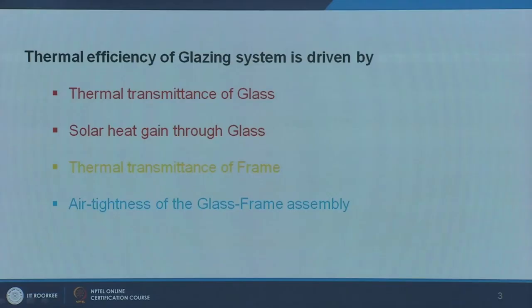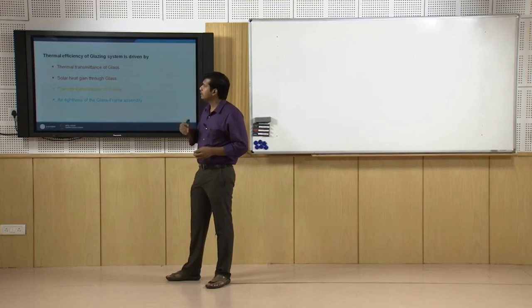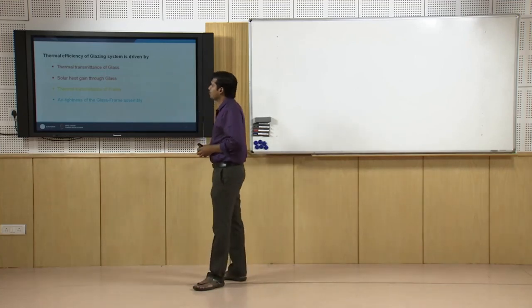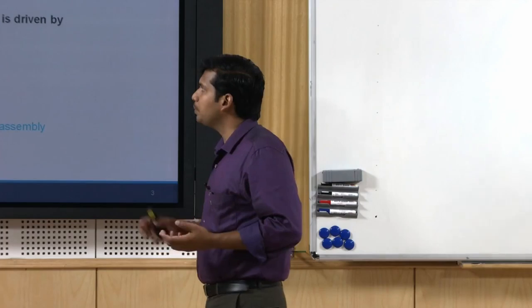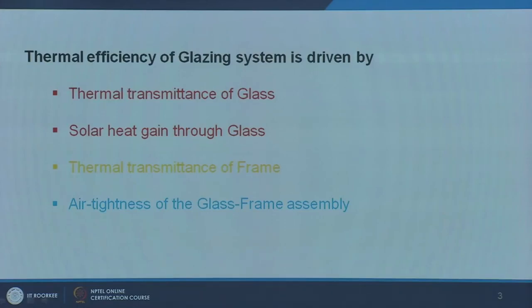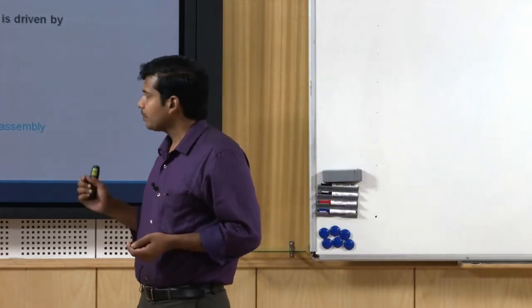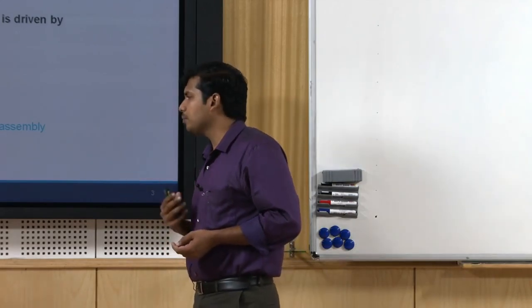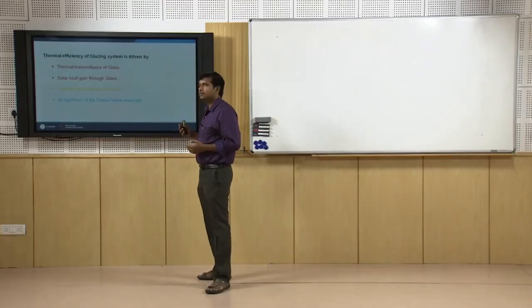The next important factor is solar heat gain through glass. This is an important factor which ranges from 0 to 1. It tells you how much radiant heat gets into the system apart from the conductive heat transfer. Next is thermal transmittance of the frame, which is no less important than the glass itself. Also crucial is the air tightness of the glass frame assembly — how well your glazing system is sealed. If you have a lot of infiltration, you will have unintended heat gains and losses.